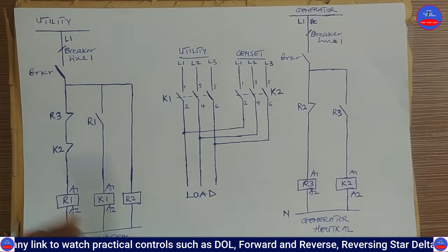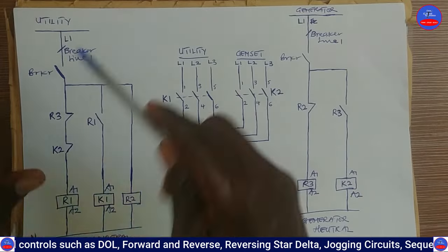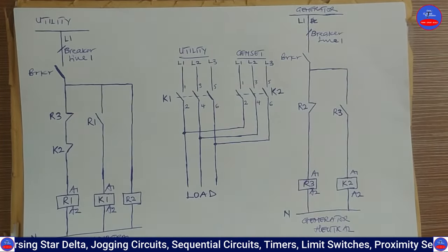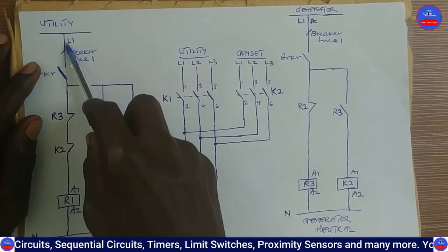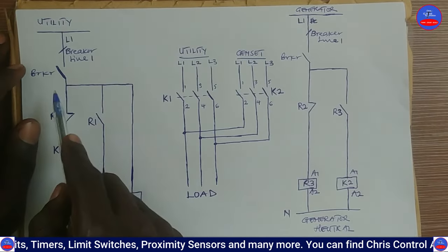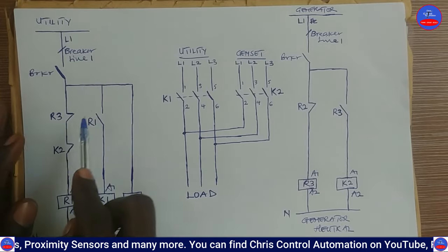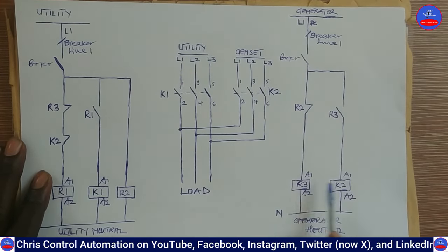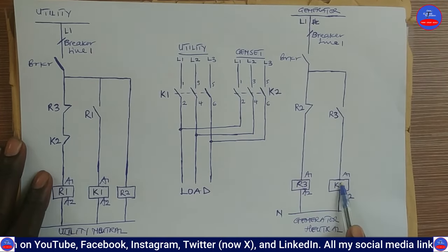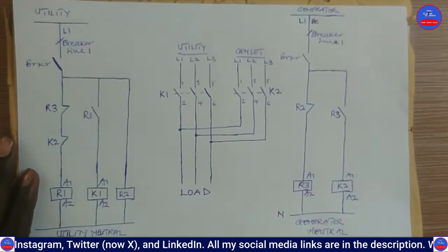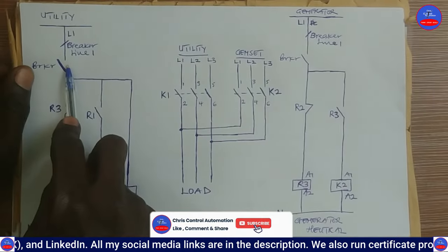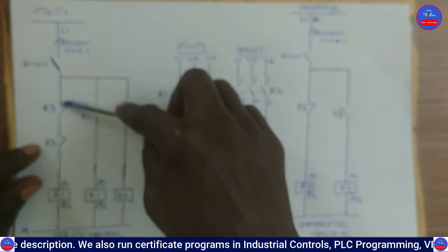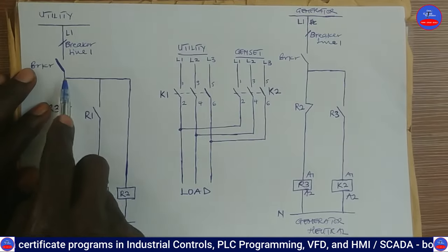Now, assuming we are operating on the generator and the main utility power comes back, the generator power will go off. Before closing the utility breaker, note that while the generator is on, R3 and K2 are energized and their contacts on the utility control side are open. So when you close the utility breaker, current cannot flow through those open contacts — it finds its way through R2 instead.